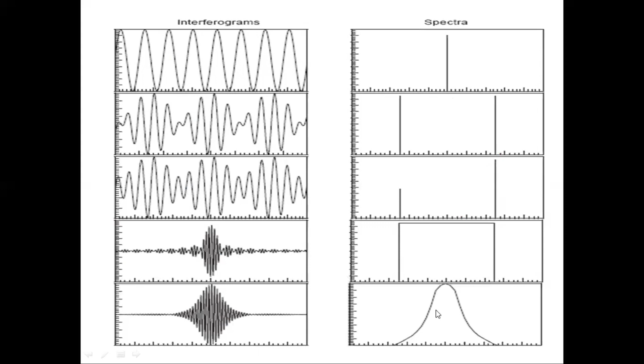Michelson interferometer. It is based on the use of an optical modulator, that is, the interferometer, which modulates radiation emitted by an IR source, producing an interferogram that has all infrared frequencies encoded into it. Just now we have seen the interferograms and spectra. The interferometer performs an optical Fourier transform on the IR radiation emitted by the IR source. The whole infrared spectrum is measured at high speed. The spectral range is continuously calibrated with a helium neon laser. Fast, extremely accurate measurements are made.